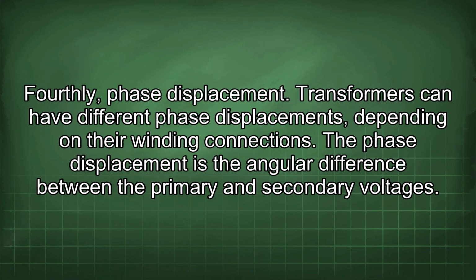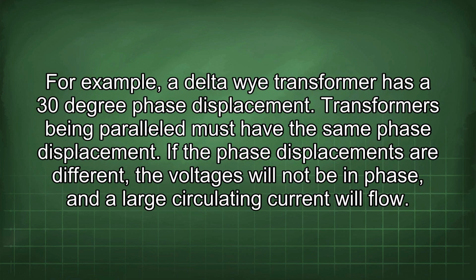Fourthly, phase displacement. Transformers can have different phase displacements depending on their winding connections. The phase displacement is the angular difference between the primary and secondary voltages. For example, a delta-Y transformer has a 30-degree phase displacement. Transformers being paralleled must have the same phase displacement. If the phase displacements are different, the voltages will not be in phase, and a large circulating current will flow.